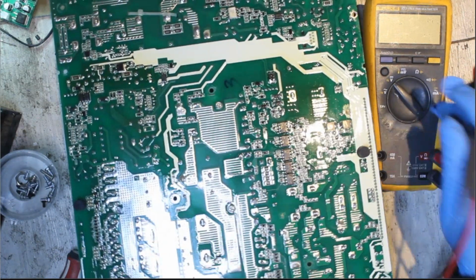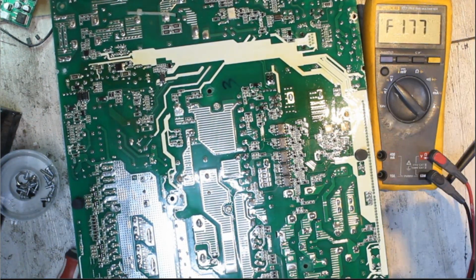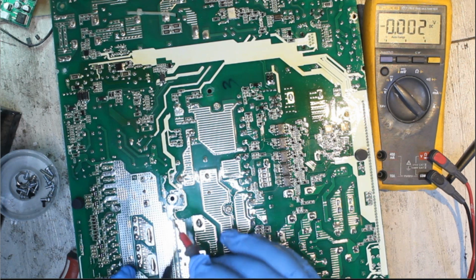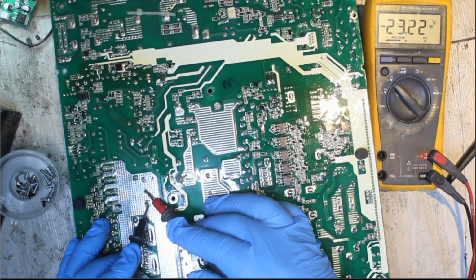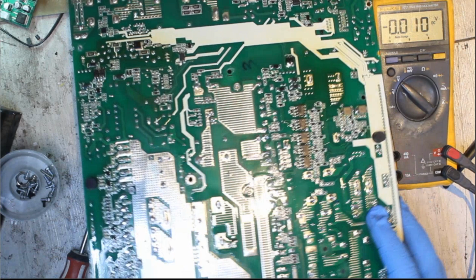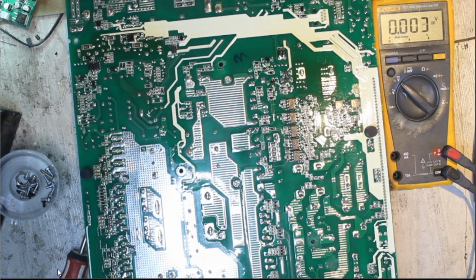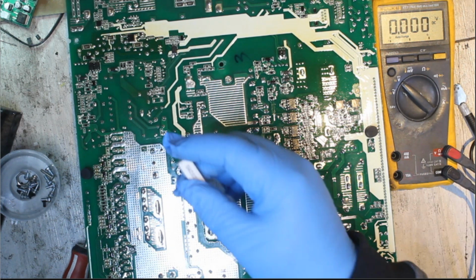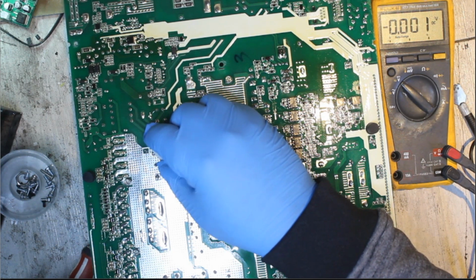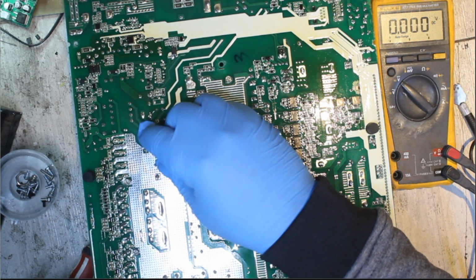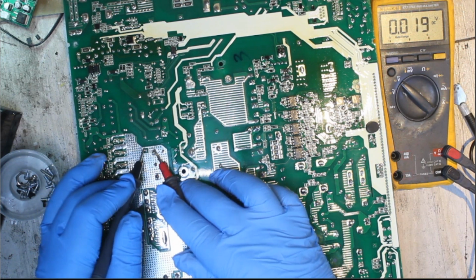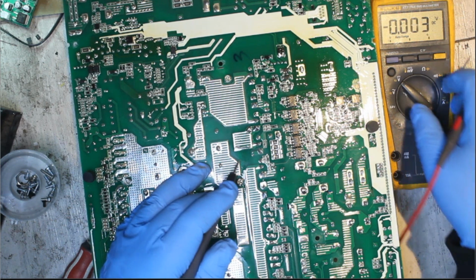But let me show you. So I've just explained about the capacitors. Just make sure that you don't have the voltage on the large capacitors and also the low voltage one. You can see we've got 23 volts there, so it's better to discharge it. Let's discharge that 24 volts. Okay, I've got the resistor. We can use the resistor to discharge. Yeah, no longer have a voltage now. You can see nothing.